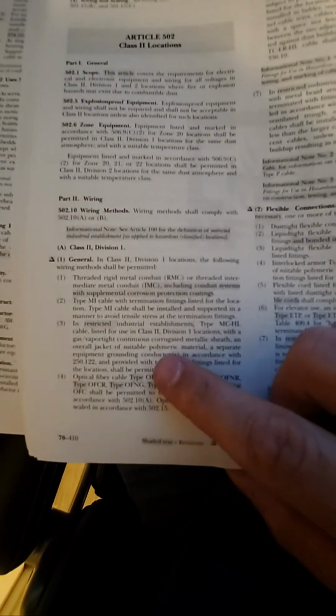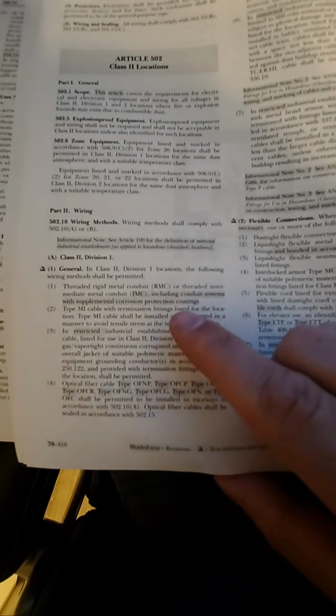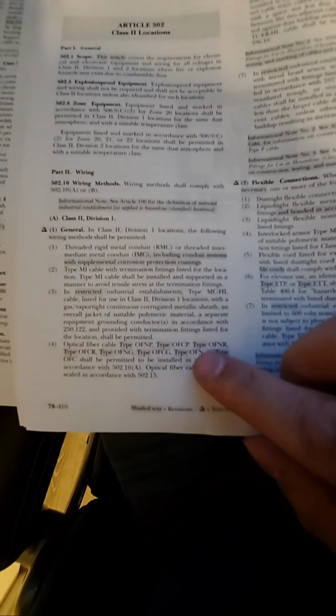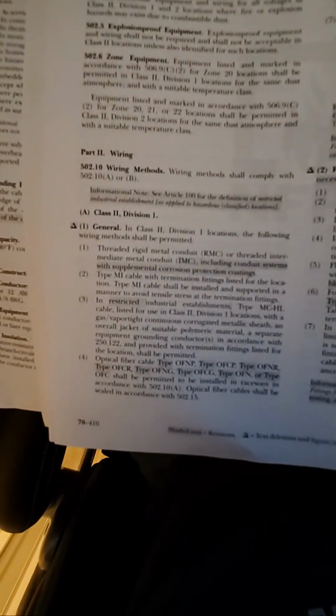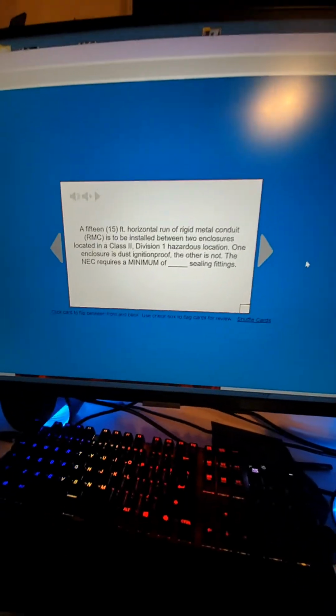We're looking for the word seal off now. Support in a manner to avoid tensile stress. I'm going to try and clean my camera, actually. Seems like it helped a little bit. We are looking for: one enclosure is dust ignition proof, the other is not. The NEC requires a minimum of blank sealing fittings.